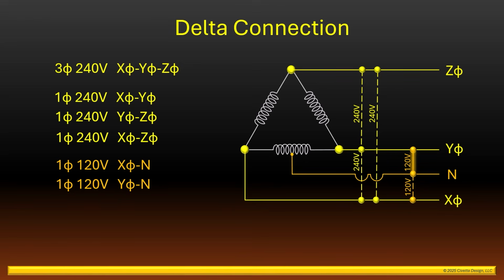Why can you not get 120 volt power by connecting the Z phase and the neutral? Because of the geometry of this type of connection, 120 volt power is only created in the windings of the center transformer where the neutral is connected, and it's only available by connecting the X phase or the Y phase with the neutral.